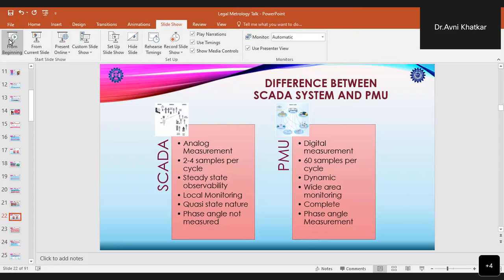So by using phasor measurements in the grid, we can ensure optimum grid synchronization and may also use the grid effectively by having islanding detection systems, by having system blackout restorations, by having microgrid management, by enabling the power system operation to optimize the energy. And we will also have cost efficiency of the grid in this way.